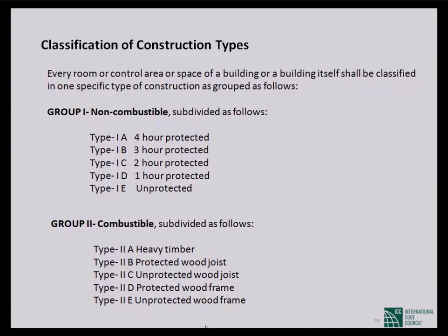At a temperature of 650, almost all steel loses half of its strength. So when the room temperature rises to roughly 750 to 800, all steel structure will collapse without any delay. So normally when steel is used, we say it is unprotected.